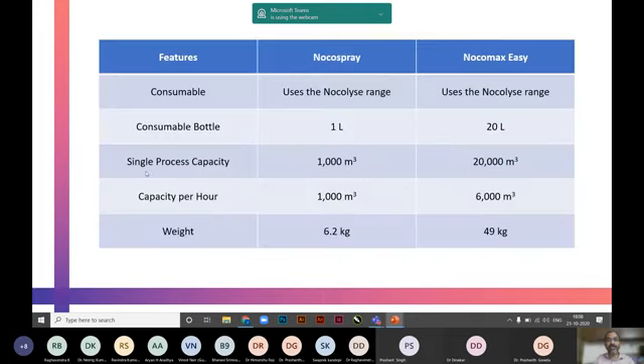The consumable used is Nocolyse, available for both machines in 1 liter and 20 liter packs. Single process capacity for Nocospray is 1000 cubic meters, and Nocomax is 20,000 cubic meters. Per hour capacity is 1000 cubic meters for Nocospray, and 6000 cubic meters per hour for Nocomax. Weight is 6.2 kg for the compact one we recommend for hospitals, while the other machine is heavier at 49 kgs.